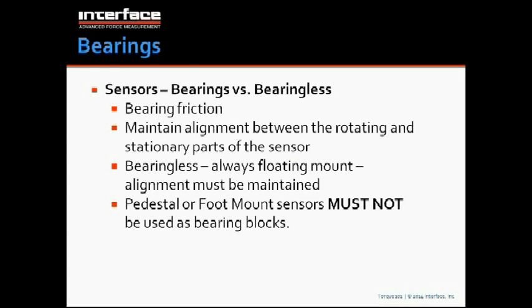Bearings versus bearingless. Some people ask, well, why would you want a bearingless sensor? Sometimes bearing friction becomes important. Imagine if you're actually trying to test bearing friction. You might not want to have the bearing friction of the sensor be part of that test, so a bearingless sensor may work. Bearings do provide alignment between the rotating and the stationary parts of the sensor.